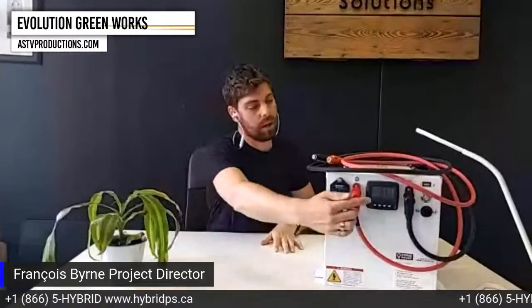Yeah, so it's really weird, you've actually got to shut the batteries off. At the battery module level, in a fault scenario, the fire department, as well as an automatic system, has to be able to fully disable, fully turn off the outputs to this battery. So what we've done here on this side, we've got a black connector, and you wire that into the rapid shutoff system. The minute that rapid shutoff system is activated, this fully shuts down the output. So we're going to be one of the only batteries on the market who are fully compliant with this.